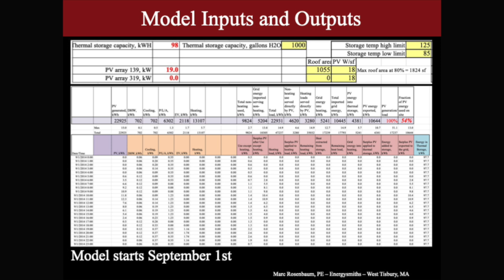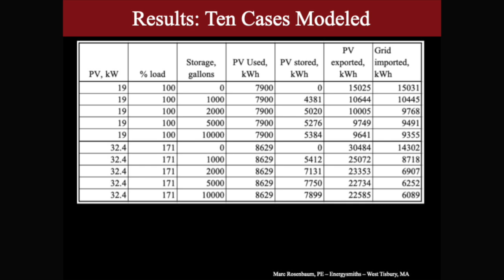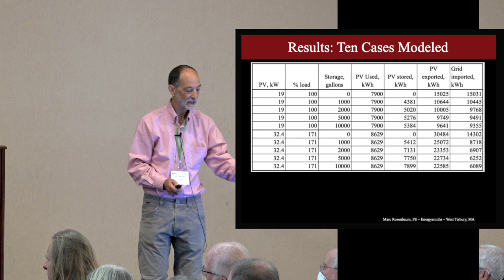But even as it is, you can shave a lot of the energy that would otherwise go to the grid and back in. So here's a bunch of cases: the first five are one slope of the roof with PVs, and 19 kilowatts is enough to make it zero net energy annually. There's storage from 0 to 10,000 gallons, showing how much PV energy is used contemporaneously—in this case, 7,900—how much is stored in that water to be used again, and how much gets exported and imported. The interesting thing to me is that the first 1,000 gallons does most of the work; by the time you get to 10,000 gallons you've only added 1,000 kilowatt-hours of storage.